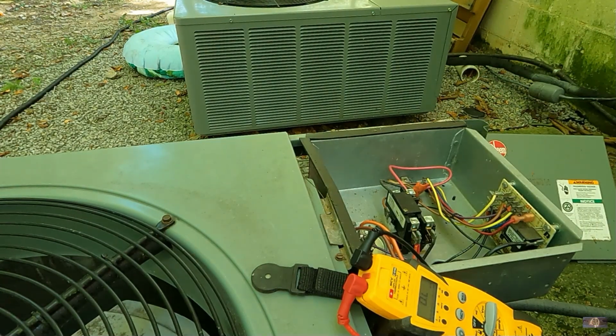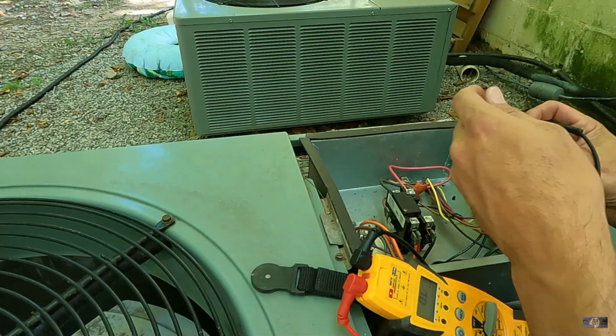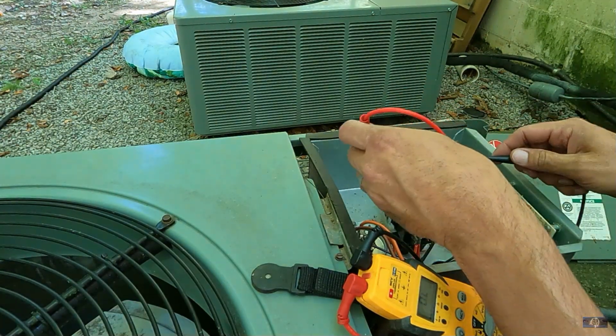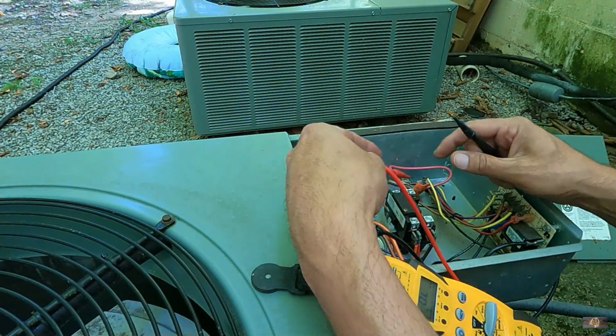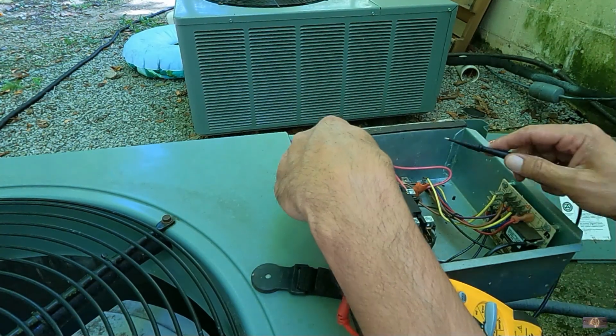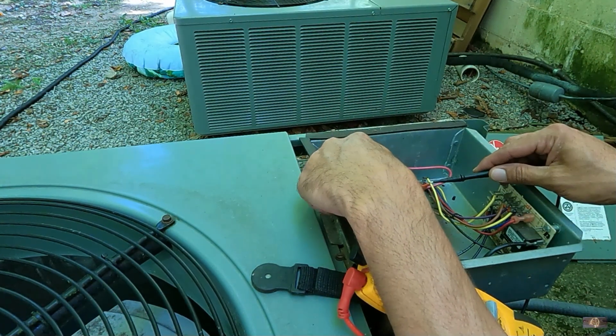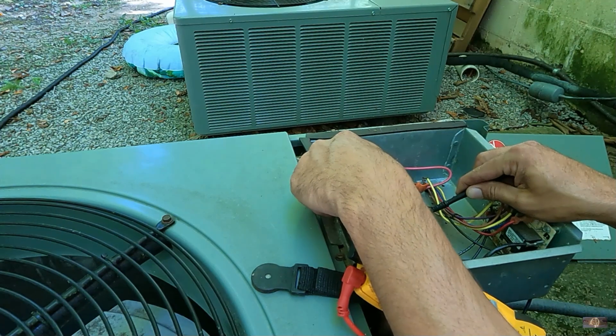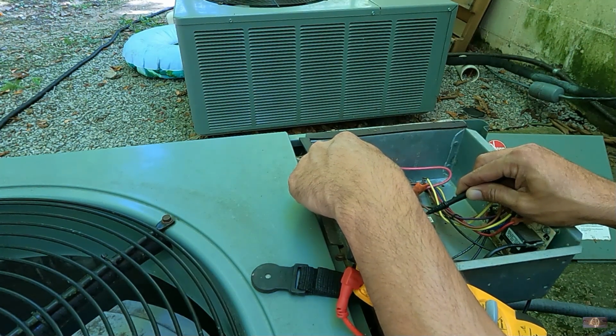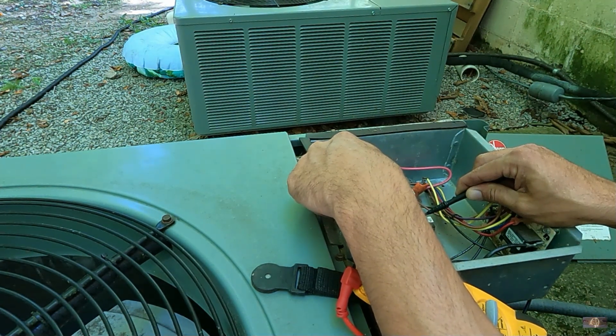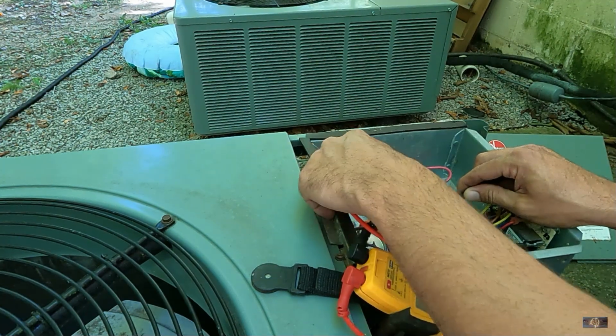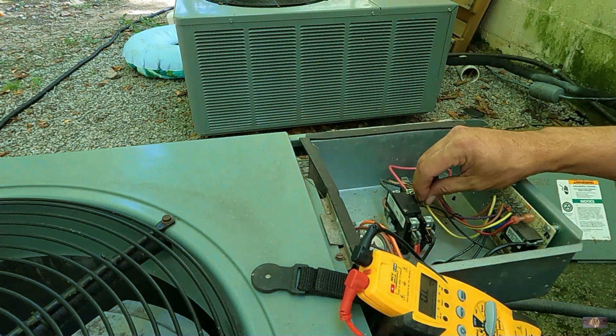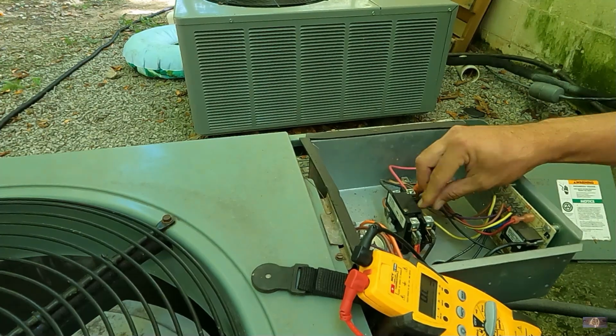I want to see what the resistance is. This is a single pole contactor, so I'd expect about 15 ohms of resistance. Anything over 20 or under 10, I'm going to recommend a replacement on it. So we're at 17.9 ohms of resistance there, so that's perfectly okay. We'll go ahead and put that back on.